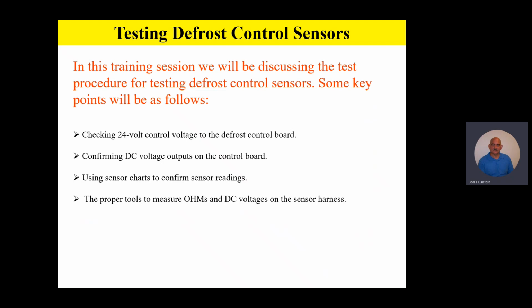Now, some of the key points will be as follows. Checking 24-volt control voltage to the defrost control board, confirming DC voltage outputs on the control board, and using the sensor charts to confirm sensor readings. In addition, we'll be talking about the proper tools to measure ohms and the DC voltages on the sensor harness.